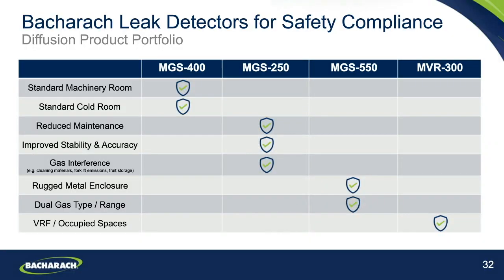So if we look across the Bacharach portfolio for leak detectors for safety compliance applications, the MGS-400 is brand new and supersedes some of the older products in the Bacharach platform, such as the MGD-100 and MGS-150. But still within there we have other options. The MGS-250 uses an infrared sensor, which can add some benefits regarding absolute stability and accuracy, and also removing cross-interference from other background gases and atmospheric effects that can influence some sensors.